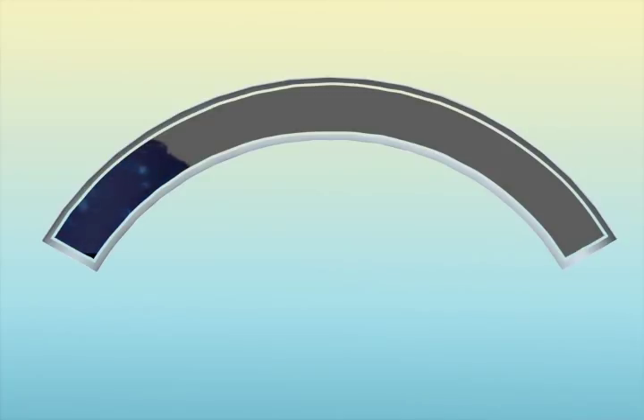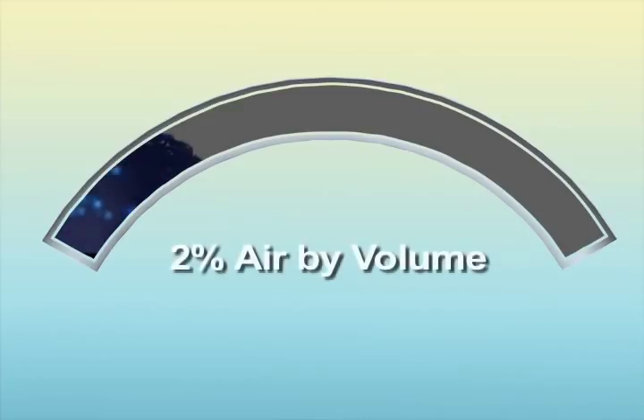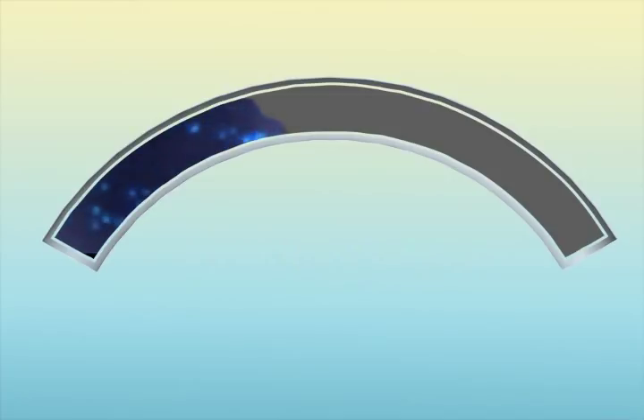Another source is the water itself. Water contains roughly two percent air by volume. During system operation, the entrained air will continuously separate out of the water and accumulate at the system high points. This two percent of air has the potential to become massive.